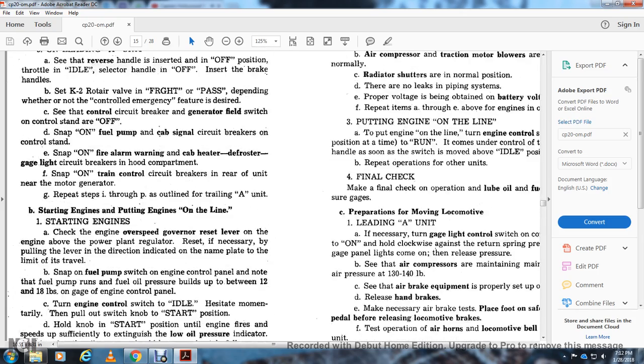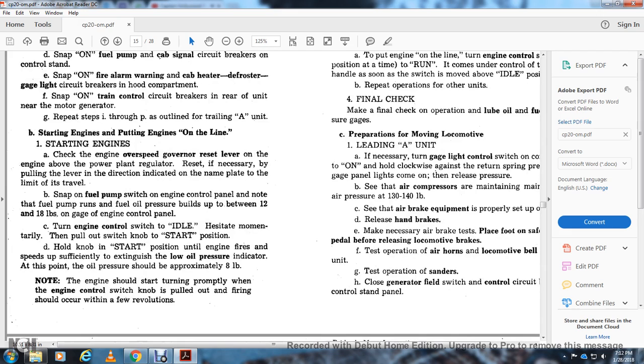Starting the engine, putting on the engines online, starting the engine, checking the overspeed governor reset on the engine power plant, with the regulated reset as necessary, by pulling the lever to directly indicate with the nameplate the limit of travel. Snap on the fuel pump, with which the engine control with the fuel pump runs, with the fuel oil pressure built up between 12 and 18 pounds on the gauge on the engine control panel.